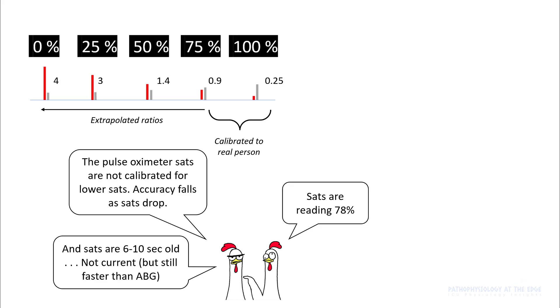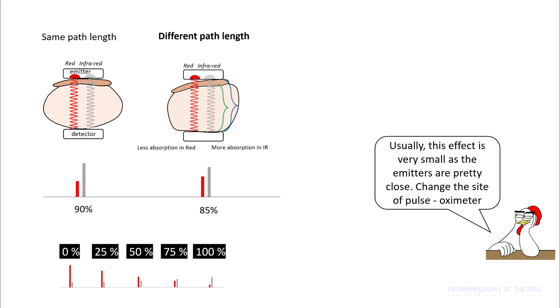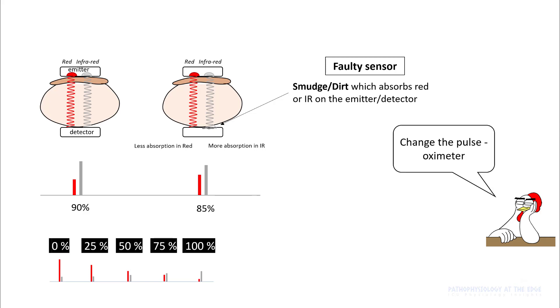The SpO2 readings are around 6 to 10 seconds old. So if you are dealing with a rapidly changing situation, your SpO2 is not current and your patient may be more hypoxemic than you think. Different path lengths can have different absorption in red and infrared and can affect your saturation — in these cases, change the site of the pulse oximeter and see if readings improve. A faulty sensor can also have differential absorption, giving rise to false readings, so change your pulse oximeter.